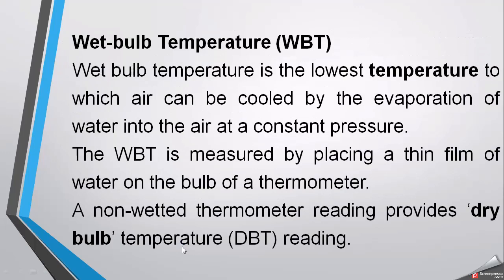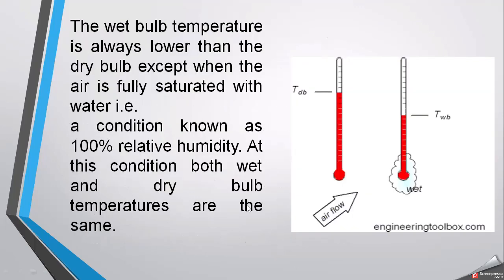Now we will explain the important term: wet bulb temperature. There are two terms — wet bulb temperature and dry bulb temperature. Wet bulb temperature is the lowest temperature to which air can be cooled by evaporation of water into the air at constant pressure. It is measured by placing a thin film of water on the bulb of a thermometer. When this water layer is present around the bulb, the temperature reading is called the wet bulb temperature.